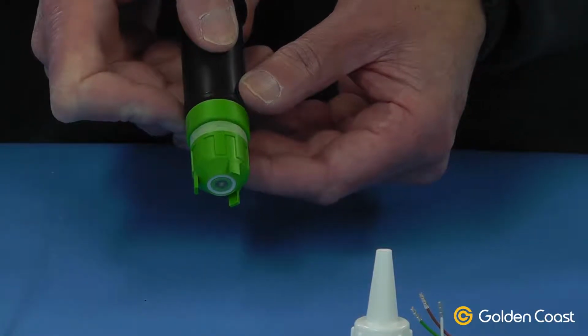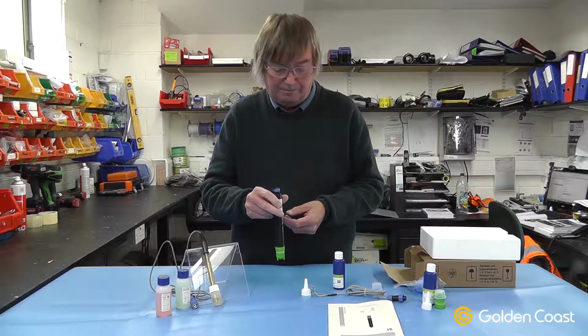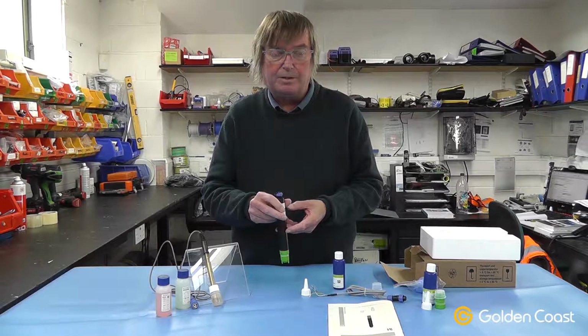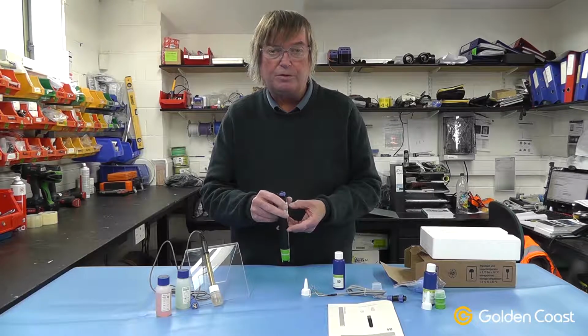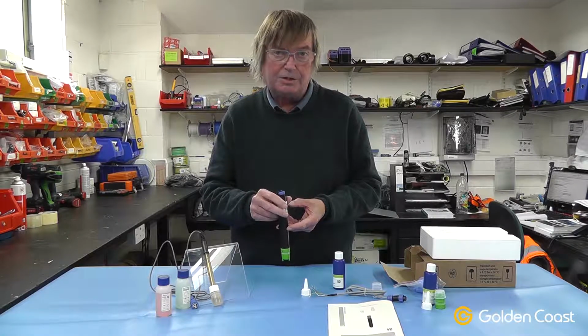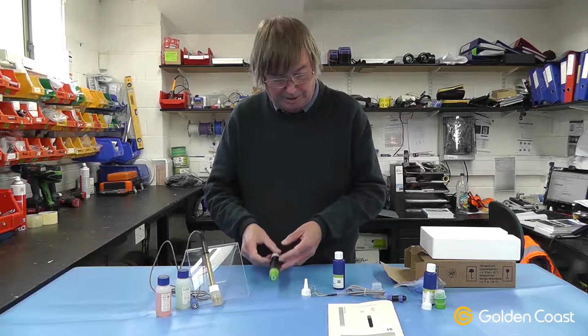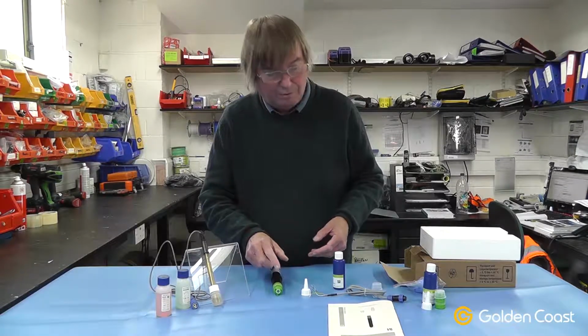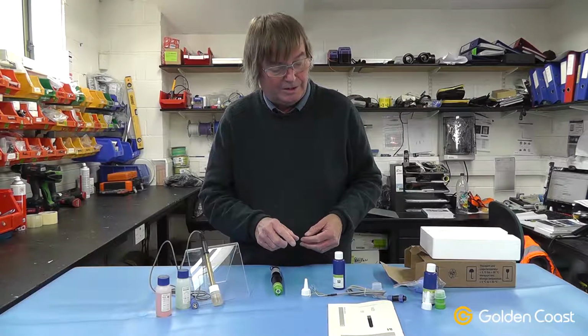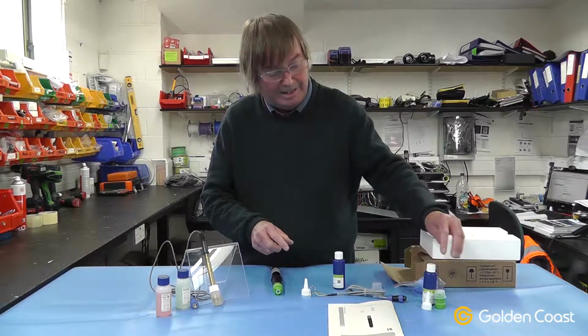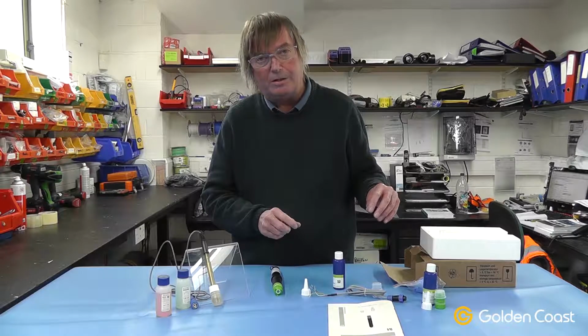The probe is then inserted into the flow cell. It should be left powered up and with the water flowing over it for 6 hours before you start looking at any calibration of it at all, if it is required. It takes a good 6 hours to come up to working temperature. If you do damage the cap, or you do maintenance on these systems, the electrolyte gel and the caps are available as a spare part.